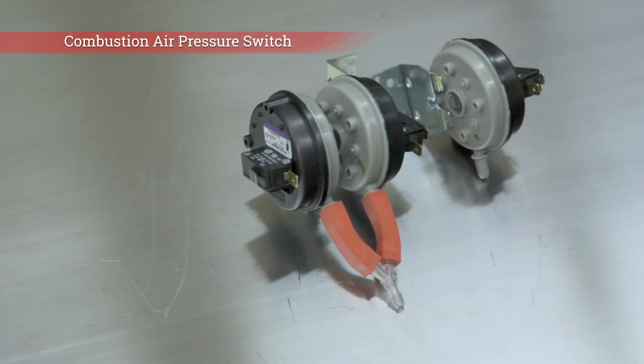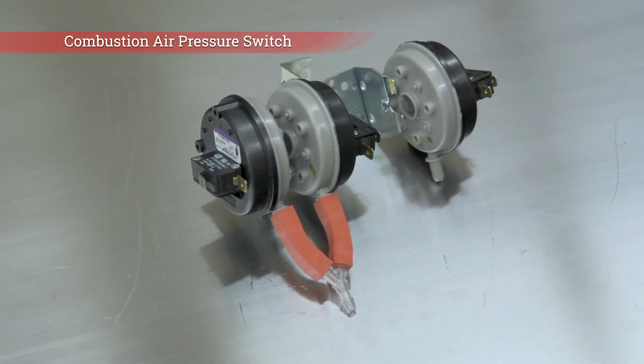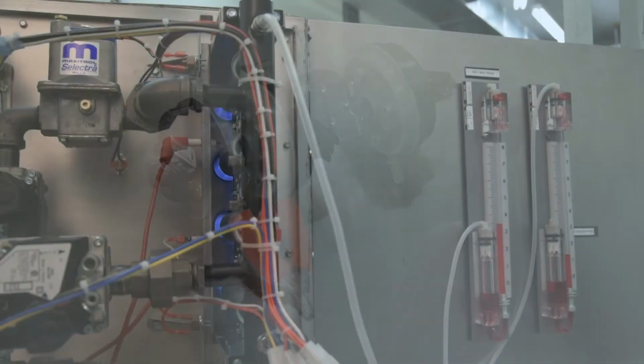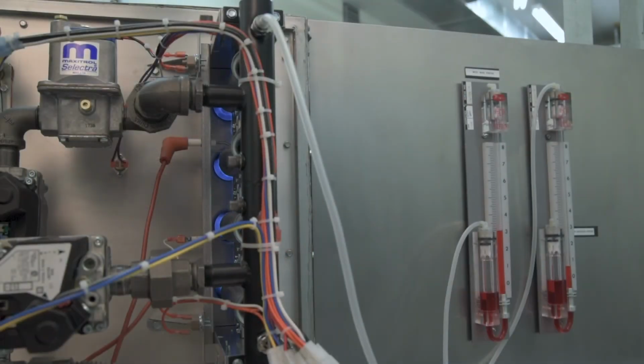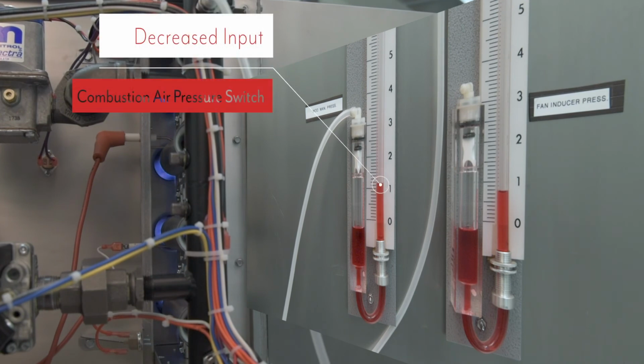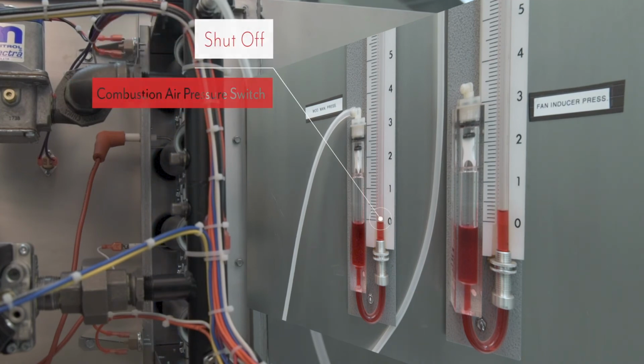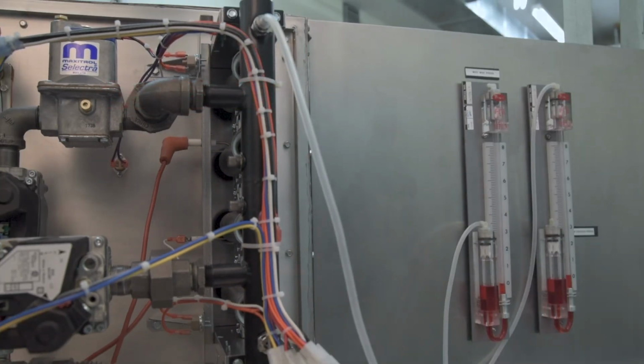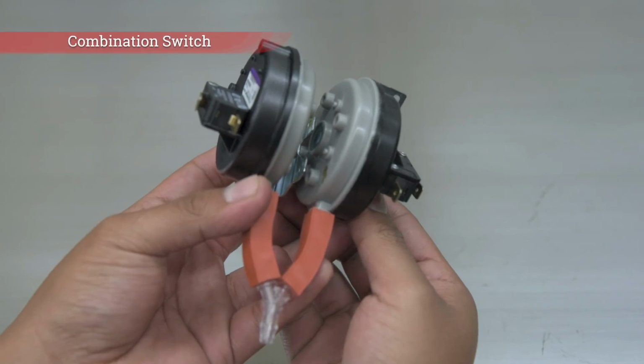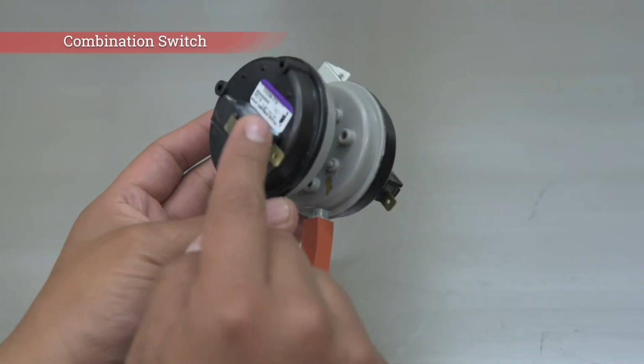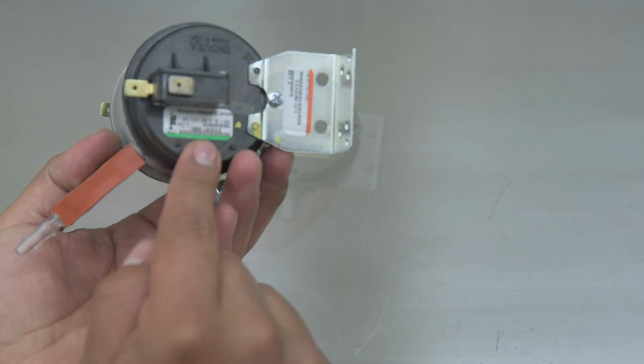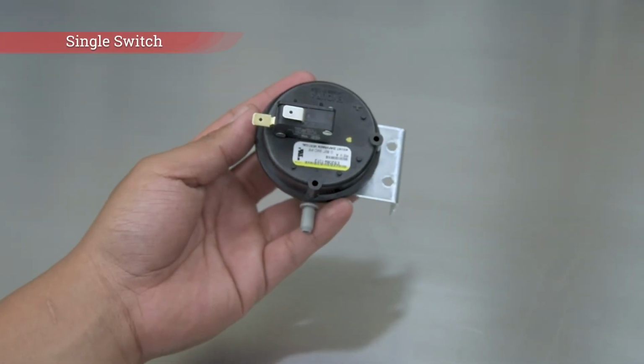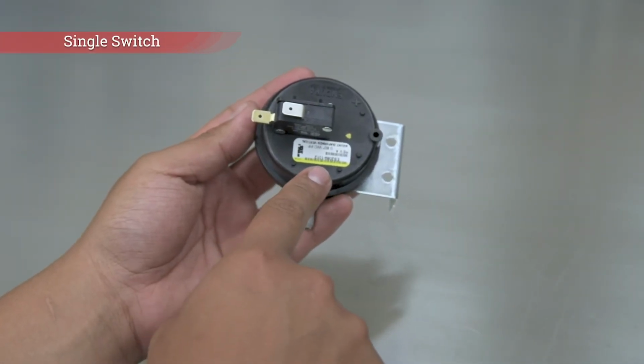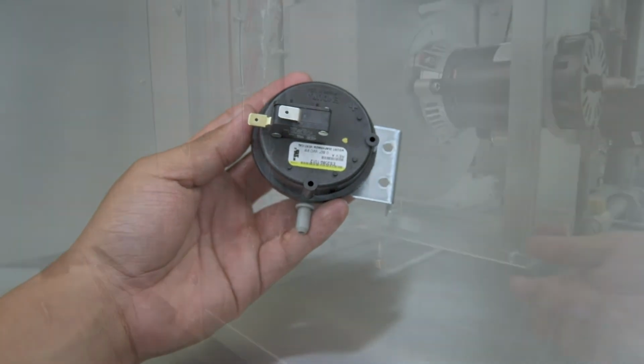The combustion air switch monitors the induced draft fan operating pressure. In the event that a block vent condition is created and the pressure value of the switch is reached, the combustion air pressure switch will either modulate the gas input or shut off the flow of gas depending on the installed control system. The combustion air switch can either be a combination switch consisting of one high and one low value, or a single switch consisting of just one high value. Values are selected by furnace model and input.